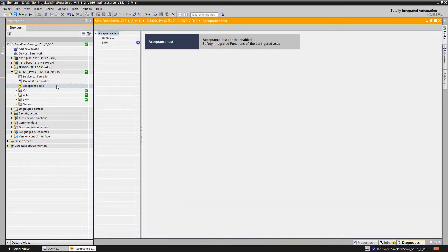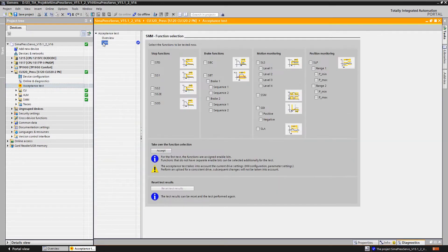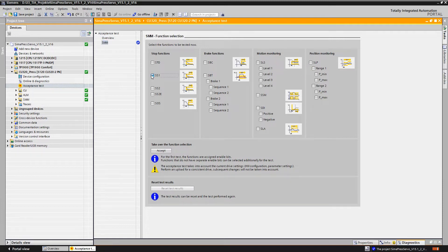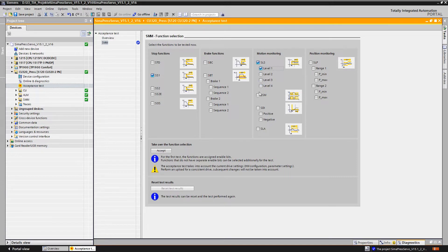To do this we first open the acceptance test from Start Drive using the Start Drive advanced option package and then select the safety functions safe stop 1 and safely limited speed with speed level 1 specifically for this drive.